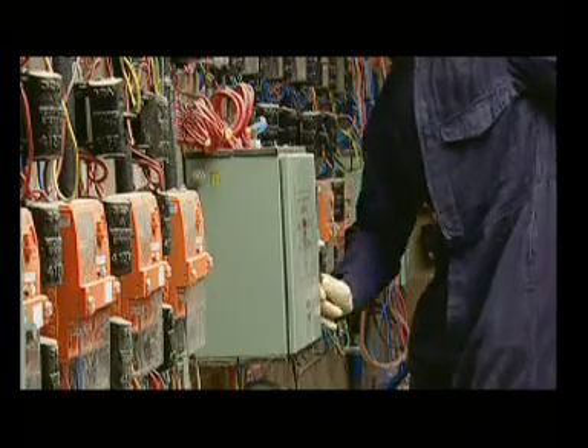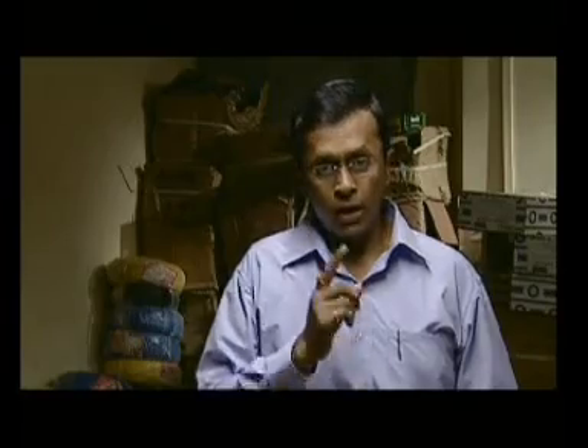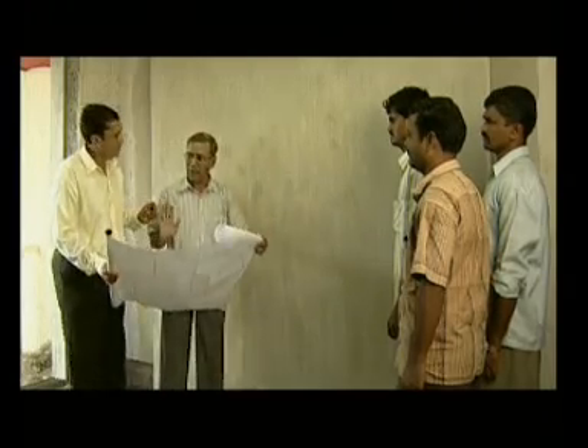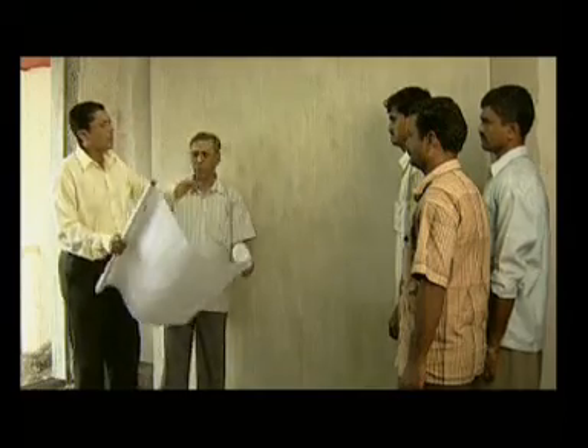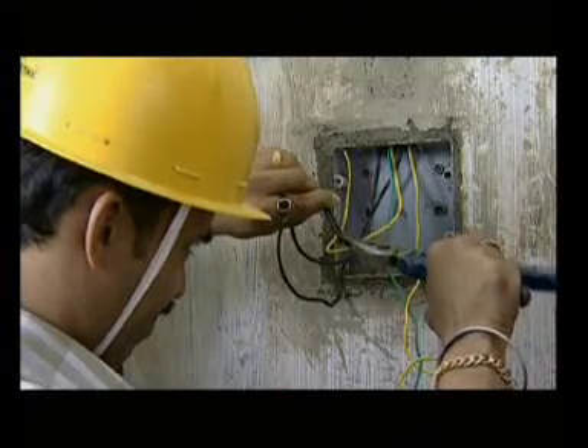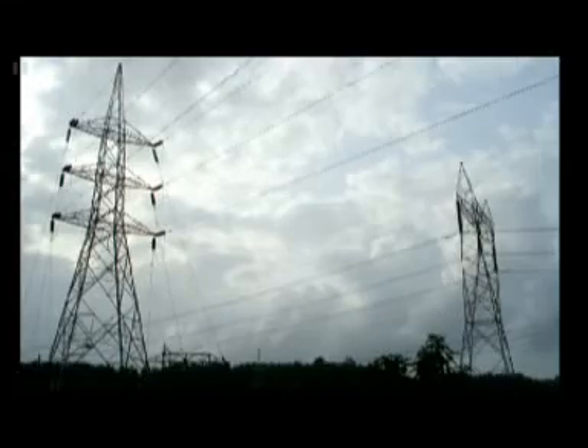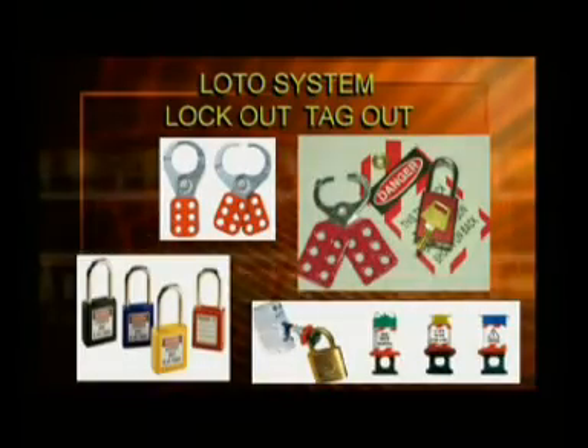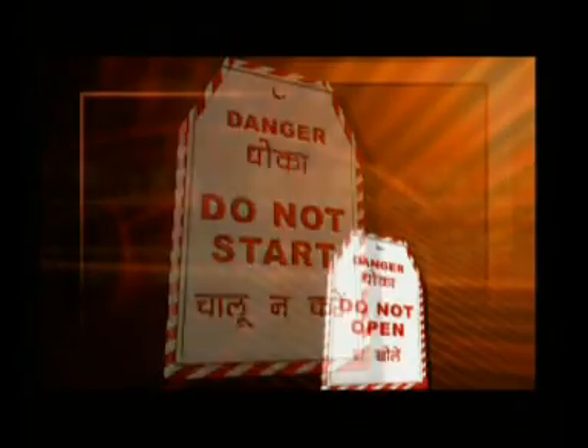To prevent electrical accidents while working with live wires, it is important to make use of proper safety equipment. And yes, the work must be carried out under the guidance of an electrical consultant and under the watchful eye of a competent electrical supervisor. In case there is any apprehension of danger, do not succumb to any pressure to begin the work. Do not wear wet or damp clothes while working with live wires. Always wear cotton clothes and avoid wearing ornaments and watches. While working with live wires, the LOTO system, that is, lockout, tagout system must be followed. Along with this, do not open, do not start, do not close labels must also be used.